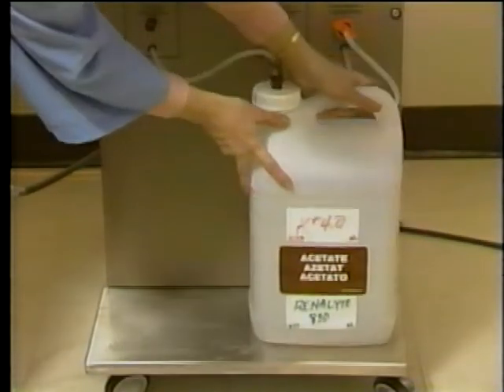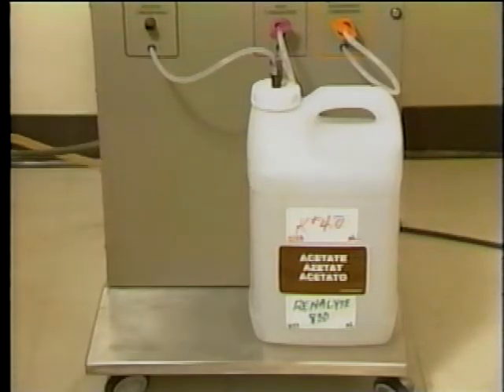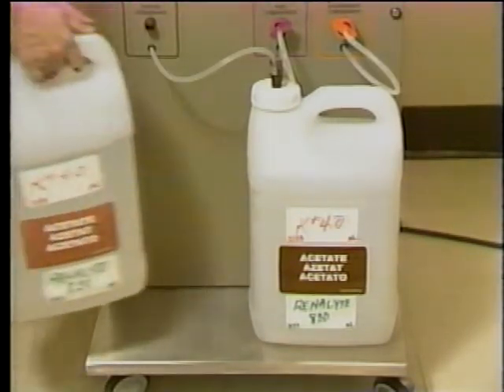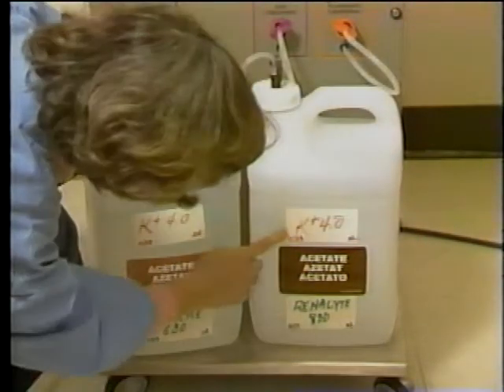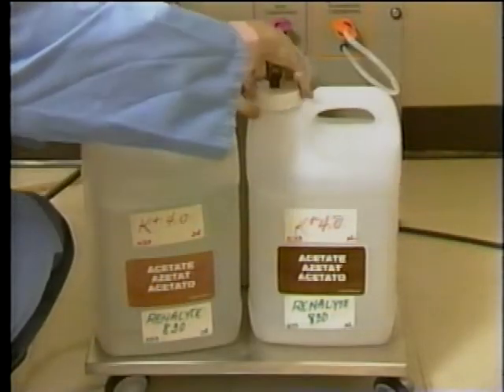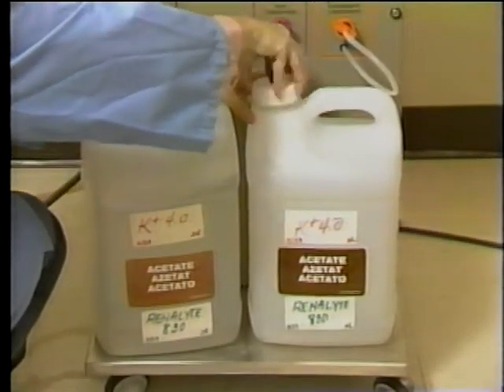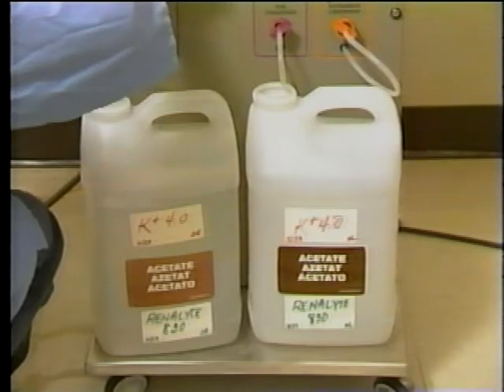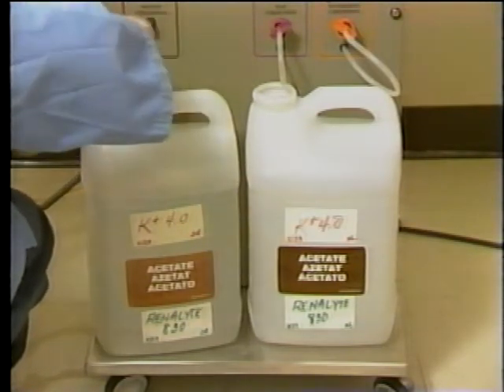Do not start a treatment without enough concentrate to complete the run. The conductivity alarm should not be used as an empty jug indicator. Interruption of a treatment to replenish the concentrate means added exposure to potential errors.